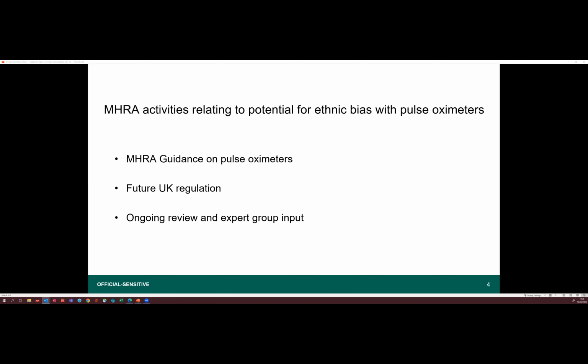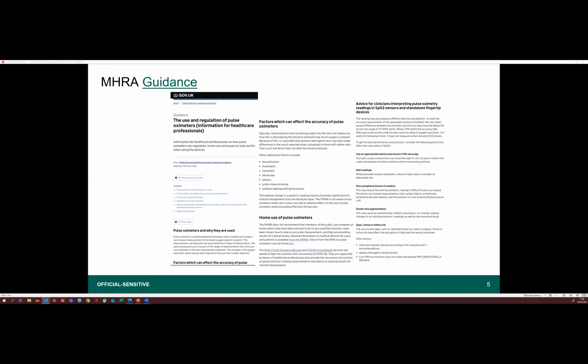There are three strands of work MHRA is involved in relating to the effect of skin pigmentation on the accuracy of pulse oximeters. In March 2021, MHRA published guidance on the use and regulation of pulse oximeters. This was published on the gov.uk web pages, and I can put a link in the chat if that's helpful. This guidance highlighted the possibility that patients with darker skin may have small differences in the result reported compared to those with lighter skin, in the context of this being one of many factors that can affect pulse oximeter readings. It advises that the relative change in a patient's reading may be of greater significance to clinical management than the absolute value, and it provides advice for clinicians interpreting pulse oximeter readings.